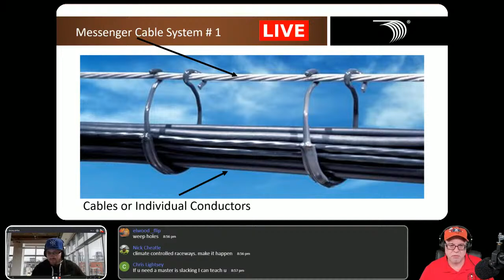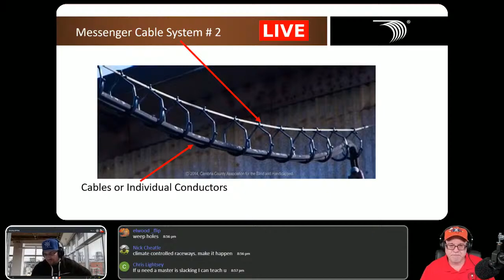This is just another example of a messenger. Jay can't see this maybe, but again, I can see it through the. Oh, you're watching the thing? Okay. Yeah, because I was looking because Peg asked, direct burial UF okay to sleeve in PVC to enter the building, and I'd say yes. Yes. Now remember, if it enters the building, you're also going to have to seal the opening again. So raceway seals to make sure that you're sealing it as it comes into the actual building, so moisture doesn't protrude into the building. But you're able to do that as well, and many people do that.